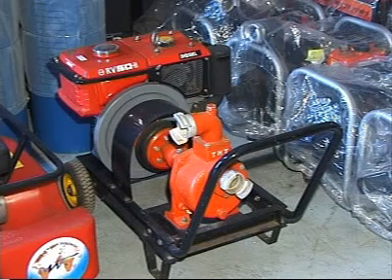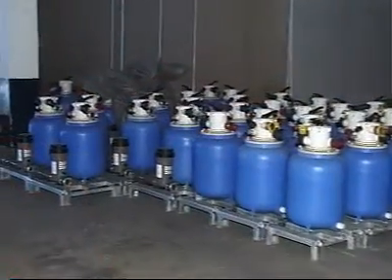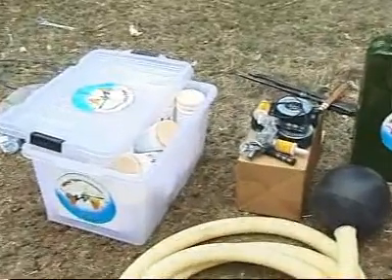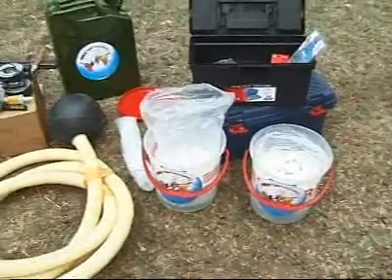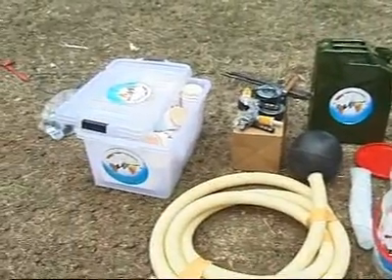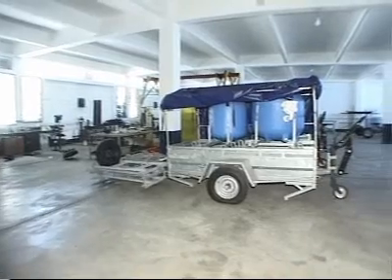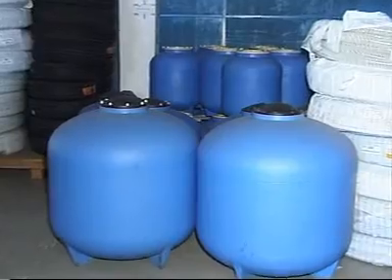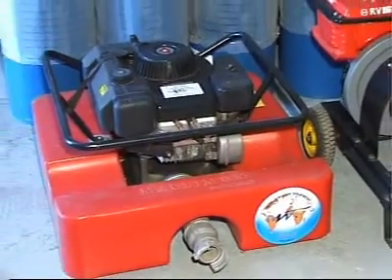All our units comprise a diesel-driven centrifugal pump, a primary sand filter, a secondary carbon filter, a chlorine dosing unit, a flocculation kit, one turbidity reduction kit with turbidity tube, and pipes for connection. On demand, our trailer or skid can be equipped with cylindrical water tank, water tower, water tap stand, submersible pump or electrical motor pump, and electrical power plant.